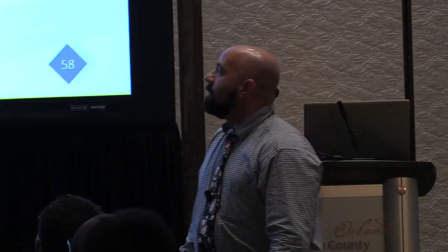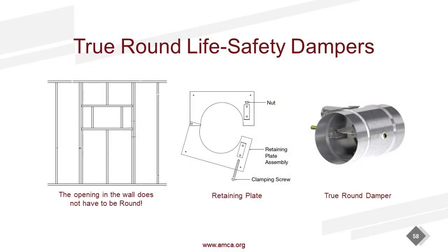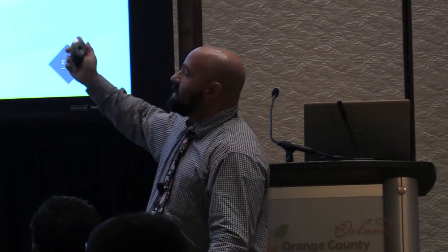I install that damper. The only caveat to true round dampers is based on the design of this plate. See this clamping screw and assembly? Well, that cannot go under the sheetrock. It has to go over the sheetrock. So there could be an aesthetic component to it for the architect. Could be a coordination between the trades. A lot of guys like to go in and hang dampers before the sheetrock's up. You can do that with a square damper. Cannot do that with a round damper. But there are benefits, cost benefits. They're usually cheaper in cost, and huge performance benefits. Think of a square damper with a round transition. That's multi-blade versus a single blade damper. So they're lower in pressure drop, lower in cost, and they are actually easier to install than a square damper.